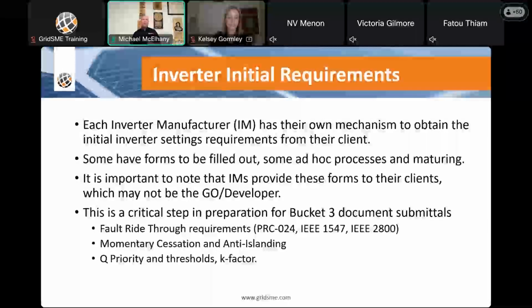So it's important to note that the inverter manufacturers provide these forms to their clients. We've got projects where the GridSME client is working directly with one inverter manufacturer on the settings, but they're working through another entity, either an O&M provider, battery owner, or battery entity who's not the inverter manufacturer, to work with the inverter manufacturer. So we need to really work closely with our clients, as early in the process as we can, to understand who their inverter manufacturer is and what the model is, so that we can help with the formulation of the inverter settings forms that need to be submitted to the inverter manufacturers. This is very critical for fault ride-through requirements, whether it's PRC 24, IEEE 1547, or 2800. And again, if it was ERCOT, it might be the NOGR requirements.